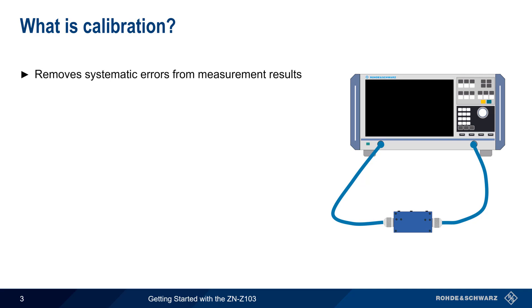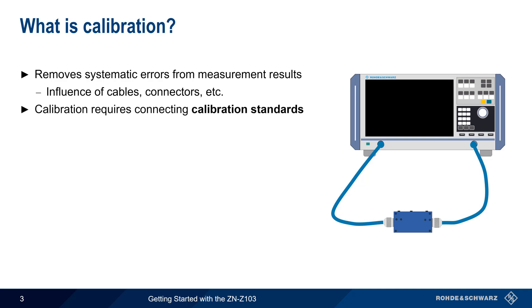Calibration is a process by which systematic errors are removed from measurement results. Examples of systematic errors are things such as the influence of cables, connectors, etc. The calibration process requires the use of calibration standards.